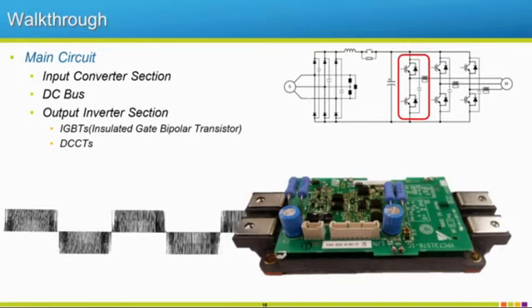So each of these sets of IGBTs are going to output a waveform. So we're building that sinusoidal or simulated sinusoidal waveform. So we have a positive and negative portion for each of these. So each of these are going to have their own waveform. So we are outputting three phase simulated AC to our motor. Since we're doing that, we now have the ability to control what our frequency is and what our average voltage is.